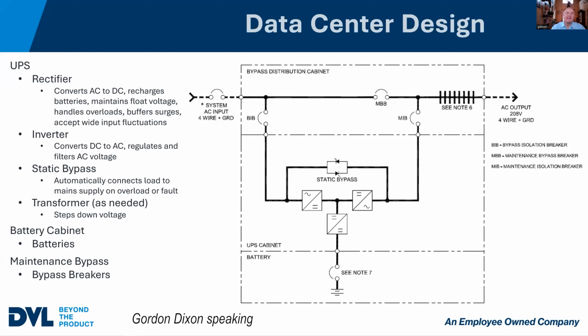The benefit being it gives you a little bit of time in case there is a delay in the generator starting. And if you're really serious about not having any downtime, that's going to be critical. So the battery cabinets are going to be usually connected to the UPS, but they don't have to. They can be VRLA batteries. VRLA is valve regulated lead acid. So those are the kinds of batteries you'll see in a vehicle, boats, RVs, same type of battery. They're generally cheaper, but they don't last quite as long.